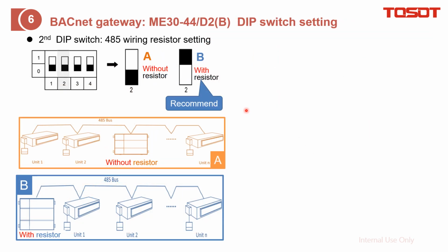To ensure the communication, for A case and B case, you need to turn on the built-in resistor to ensure it. For the second dip for RS485, for situation A it is okay, but for B, it is located at the top or tail, so you need to turn on the built-in resistor to ensure the communication. Both connections are acceptable, but we recommend this B option.